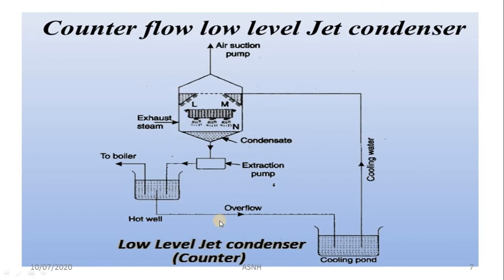So now here you will get an idea about the direction of the steam, which is coming from the bottom of the shell, and the air extraction pump is placed on the top side of the shell. The main function of the air extraction pump is to remove the air or excess air available in the condenser shell in order to maintain the proper vacuum inside. For satisfactory operation of any kind of condenser, we must maintain a proper vacuum inside the shell. So if some air remains in the shell, we must remove it. That's why the air extraction pump is needed, and in the case of the counter flow, it is placed on the top side of the shell.